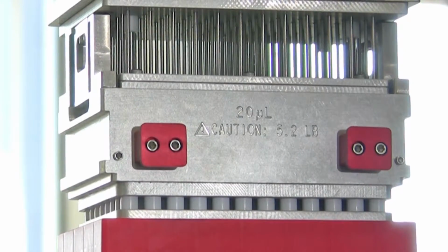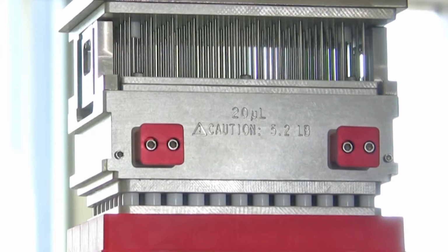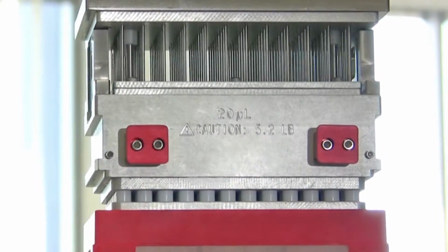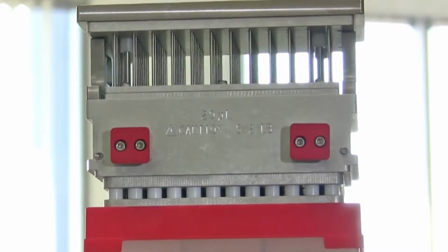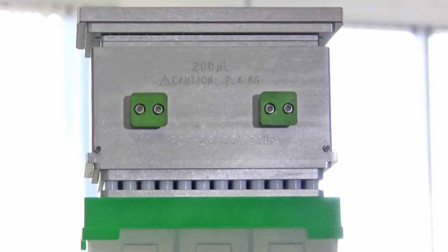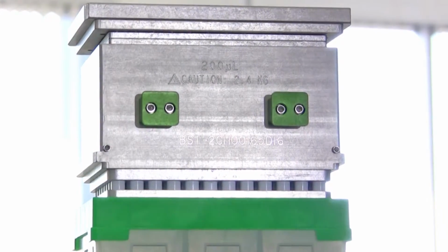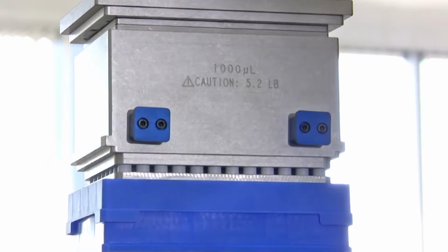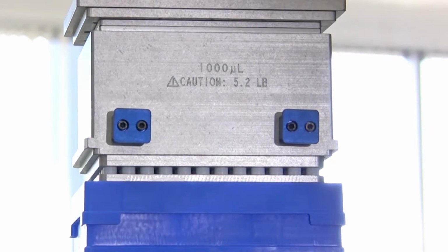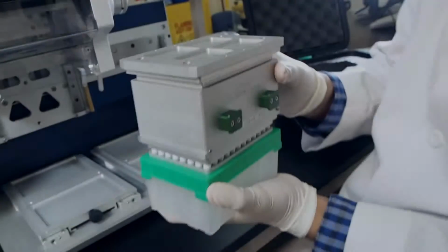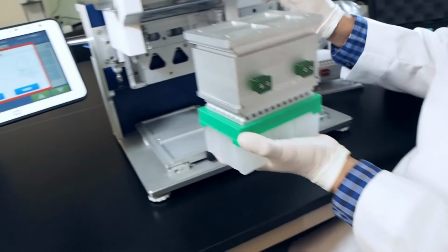The 0.5 to 20 microliter head has small red pull handles on the front. It's packed on a tip box with a red lid. The 5 to 200 microliter head has green pulls and a box with a green lid. And the 100 to 1000 microliter head has blue pulls and a blue lidded box. Heads weigh 5.2 pounds each.